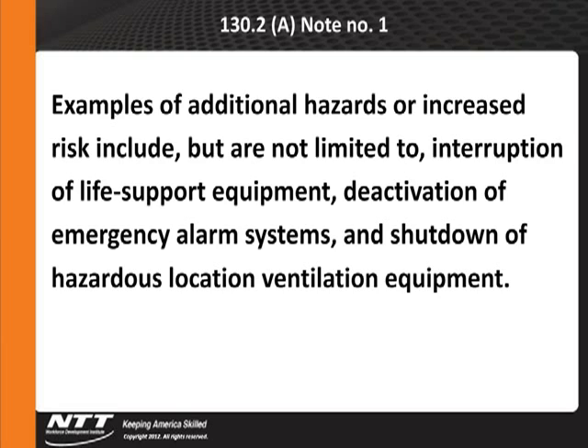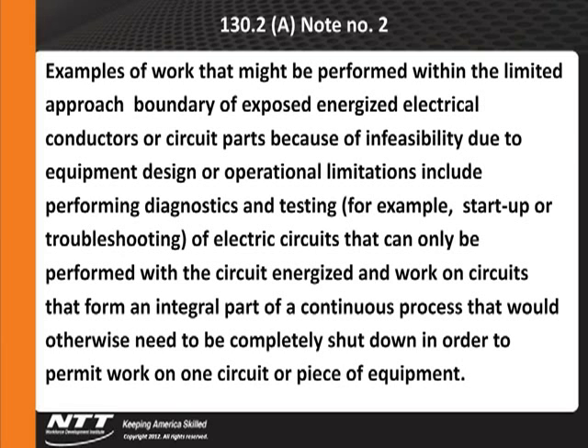Examples of work that might be performed within the limited approach boundary of exposed energized electrical conductors or circuit parts because of infeasibility due to equipment design or operational limitations include performing diagnostics and testing. Well, it has to be on to do a voltage test.